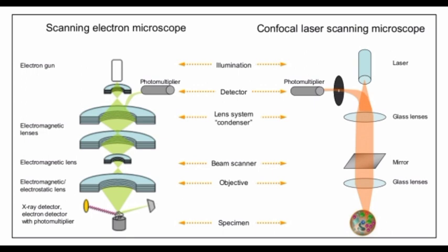The beam interacts with the specimen and emitted electrons are detected in specific detectors and amplified using photomultiplier tubes. Emitted radiation such as X-rays is detected in accordingly designed detectors. Every scanned pixel on the specimen represents a pixel on the screen. Important: there is no imaging device such as a CCD camera in SEM.